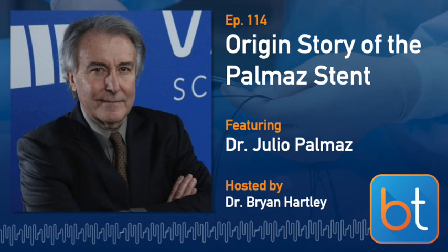And of course, then all the technical issues about doing that in a microscopic device came up. But after playing a lot with those things and making little models, I decided, why am I going crazy trying to use little stuff? I could make this like 100 times larger and then do all my calculations about free area versus metal area and how that changes with expansion, in large models. I started working with cardboard, and that was actually a good solution. I figured out the simple geometries, how the expanded area would change with increasing diameters, and how the slot length influenced the radial strength.